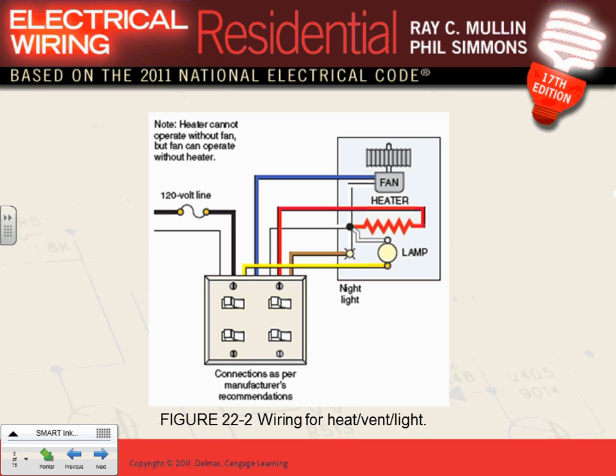So this is a combo. Since this is a combo, guys, here's what the manufacturer will tell you. When you buy this, they will tell you from the product, provide a 20 amp circuit with 12-2 fed to it. Done. When you have a combo like this, guys, anybody have seen this? Jeff, you said you have seen them, right? And you have, so look what this has. It has a fan. It has also a heater, and it has a lamp, a regular lamp, and a night lamp. So if you have little kids, you appreciate what a night lamp is. You leave the light in the bathroom on for the kids so they don't do it in the closet. You know. So that's what this combo is.